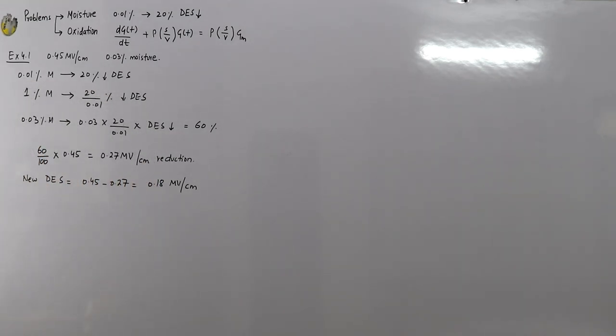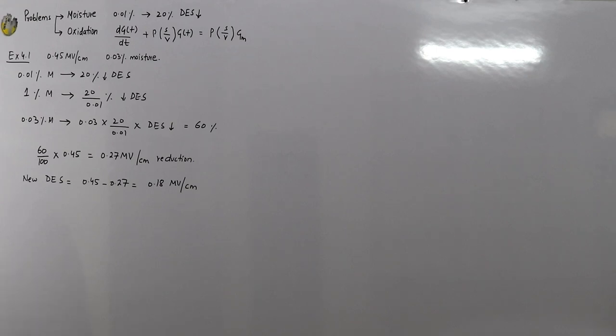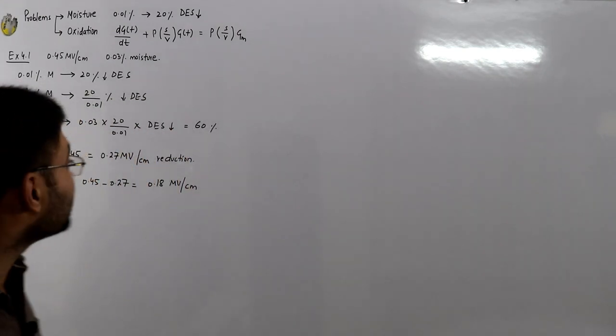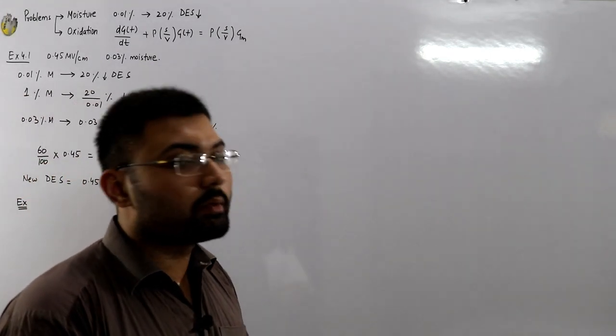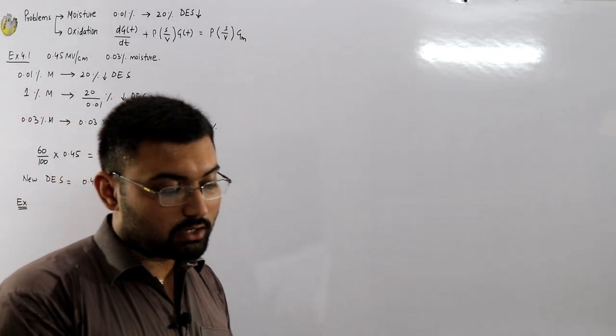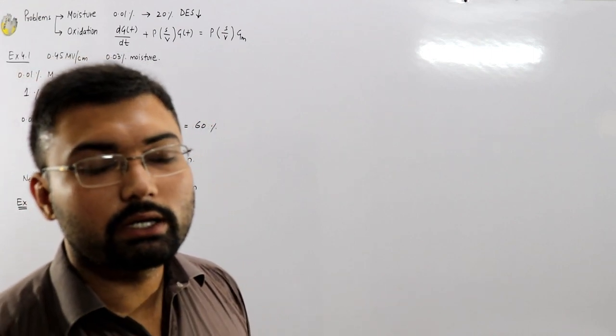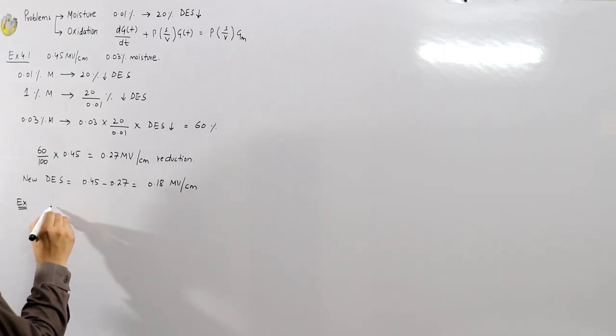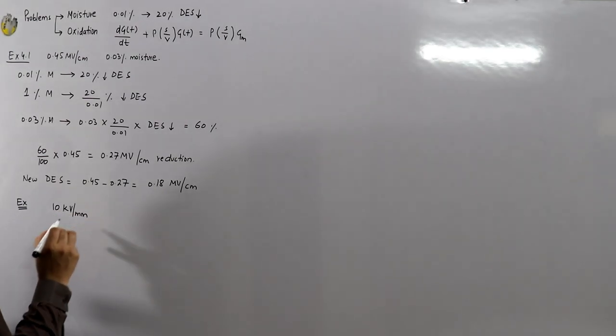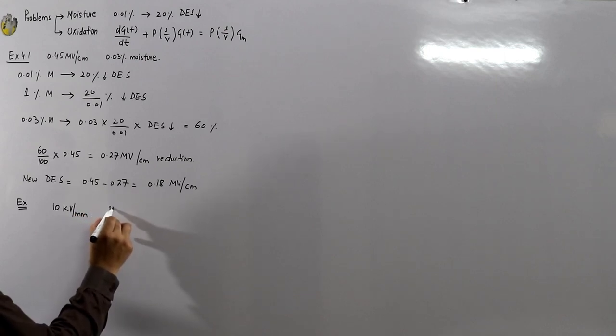Similarly, the problem can be given in the converse manner: you are given the dielectric strength and asked for the moisture content. For example, a company like Pesco gives you a sample of transformer oil and asks you to find the moisture content. When you measure it, the dielectric strength comes out to be 10 kilovolt per millimeter — that is the new dielectric strength. You need to find the moisture content, knowing the fresh sample should be 15 kilovolt per millimeter.